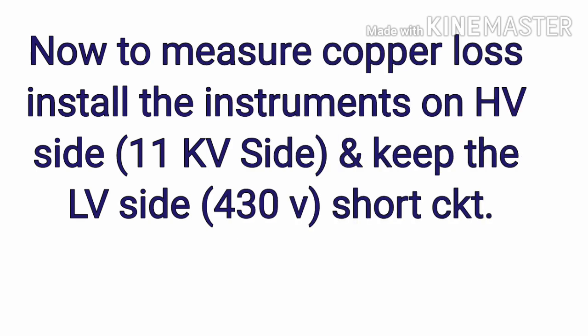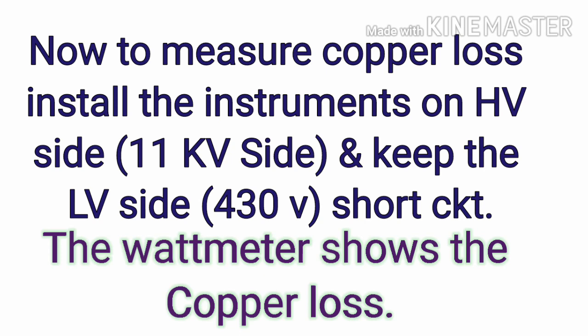Now to measure copper loss, we have to do the short circuit test. Then we will work with the 11 kilovolt side, that is my primary winding. We will set up all the instruments on the high voltage side, that is my 11 kilovolt, and we will short circuit the 430 volt side, that is my low voltage side, and thus we can measure the copper loss. The wattmeter reading will show the copper loss.